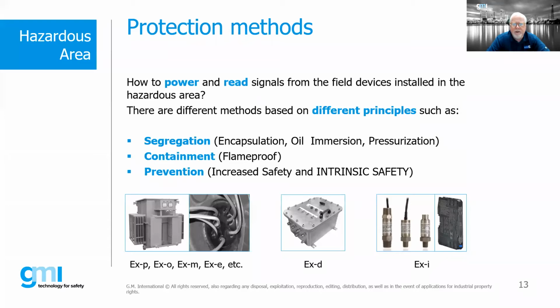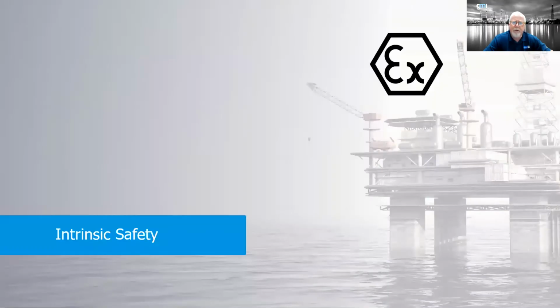So prevention is basically removing, in effect, any potential arcing or sparking. And we do that by the use of increased safety enclosures with creepage and clearance distances, and with intrinsic safety, where we're limiting the amount of energy. So these are the basic concepts. Now, there are other protection concepts, but they all pretty much fall within these concepts, if you will.